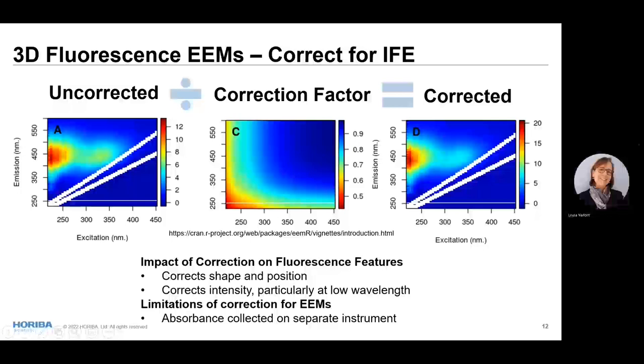To correct a 3D EEM, you collect the absorbance spectrum, calculate the entire IFE contour, divide the uncorrected EEM by the IFE contour, and then obtain corrected data. This seems like a very promising step, but what are the limitations? For standard EEMs, the absorbance correction is collected on a different instrument. Temperature changes, optical path differences, et cetera, can all impact what we'll call the goodness of the correction.